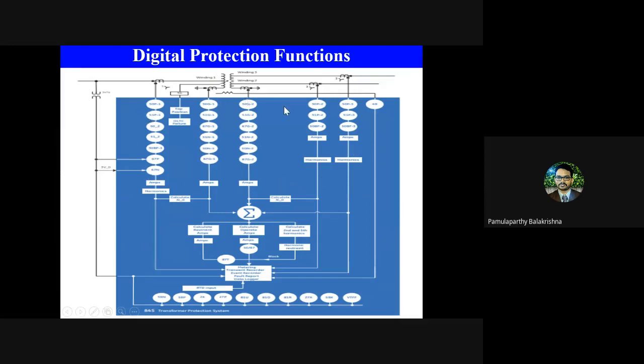a flexible manner, in the sense that each protection function is a separate logic or a separate code, and each function will enable or disable automatically based on the presence of the corresponding input. Okay, so for example, usually as I told, in a relay you will get current input, voltage input, and from that you compute frequency, power, energy, all those things.